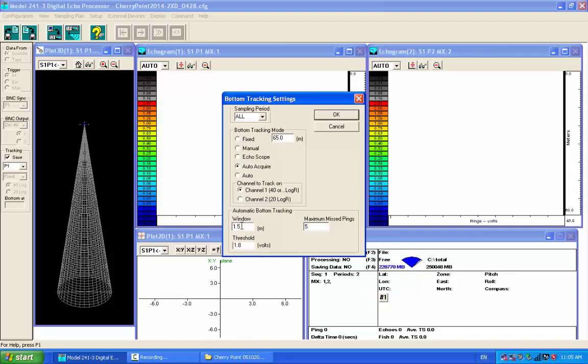Because depending what your window is, I dialed it in, and yeah, it does reduce the dead zone, but it didn't reduce it enough for that. No, not enough for that. But certainly with this bottom window, you could see in this one, anything within three-quarters of a meter of the bottom just wouldn't be recorded in the data set. If I did fixed and then very carefully marked the bottom, then my limitation is really just that c-tau over 2 pulse width or the shadow, basically those two in combination, which may approximate or come close to that sort of thing.